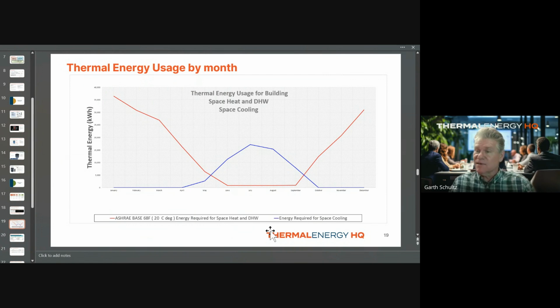We can utilize their existing 2-pipe system throughout the building that used to run the boiler loads. Now it can run not only the space heating, but also the distribution consoles located inside, which act like little heat pumps, fan coil units that are liquid-to-air distribution consoles, giving us storage capability. We don't have to go up to tall, high boiler temperatures, we can manage all that thermal load anywhere from 90 to 120 or 130 Fahrenheit, the common operating parameters of a chiller and/or an air source heat pump.